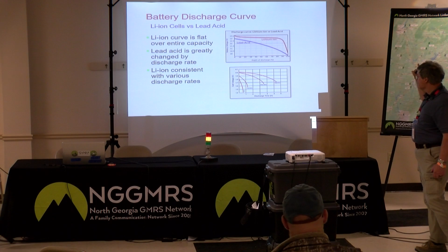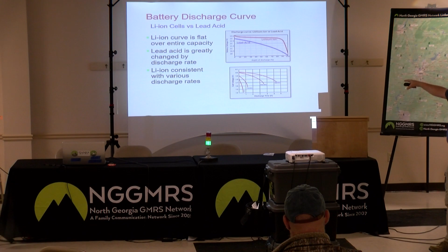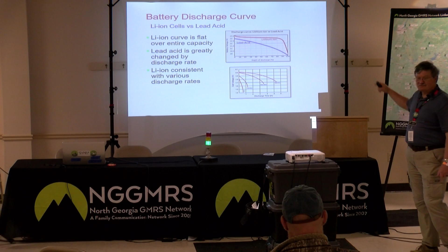That's why it's important. I mentioned knowing how your load responds - maybe your load doesn't care, but if it does, that might be a good reason to go to lithium-ion or lithium iron phosphate instead of lead acid. The lithium battery voltage is pretty constant regardless of discharge rate, whereas with lead acid, shown on these red curves, it can change drastically according to how heavily you load the battery. There are a lot of battery design decisions that go into lead acid, depending on whether you need a battery discharged in 15 minutes for an uninterruptible power system, or one you run for 20 hours, because they do things to get better performance depending on the application.